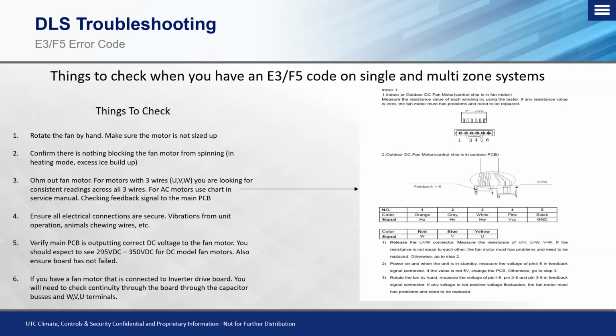So if you look on here, you have a breakdown between the W, V, and U wires and the 5-pin wires on there. Okay, now you can see in this case, number 5 or pin 5 on there is your black wire, that's your ground. Okay, so as we're going through, like I said, if you look at the bullet points in the bottom here, there should be 3 there. The first one's going to be if you have the U, V, and W, you want to make sure that you measure the resistance between the U, V, and W wires, and we're looking for consistency.